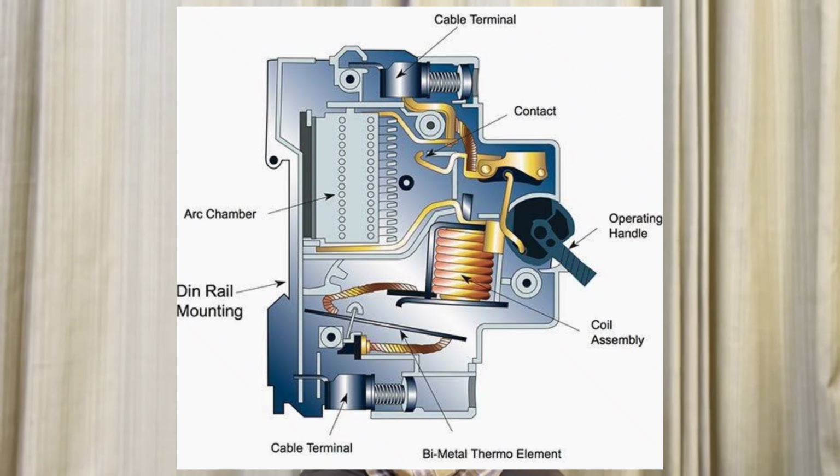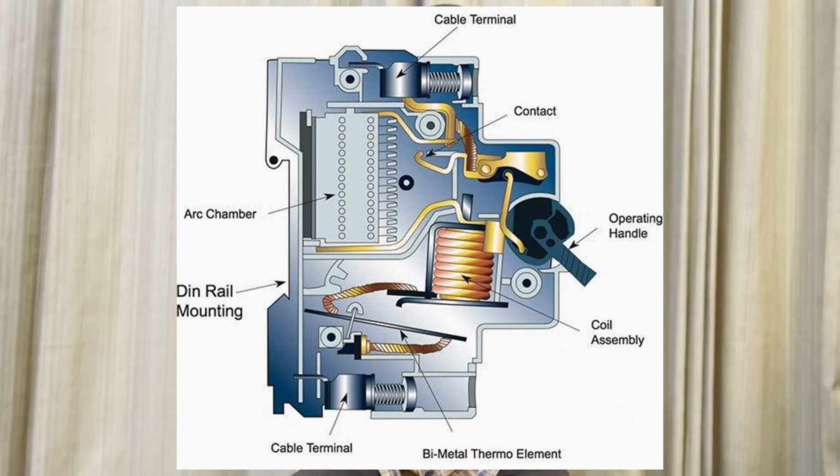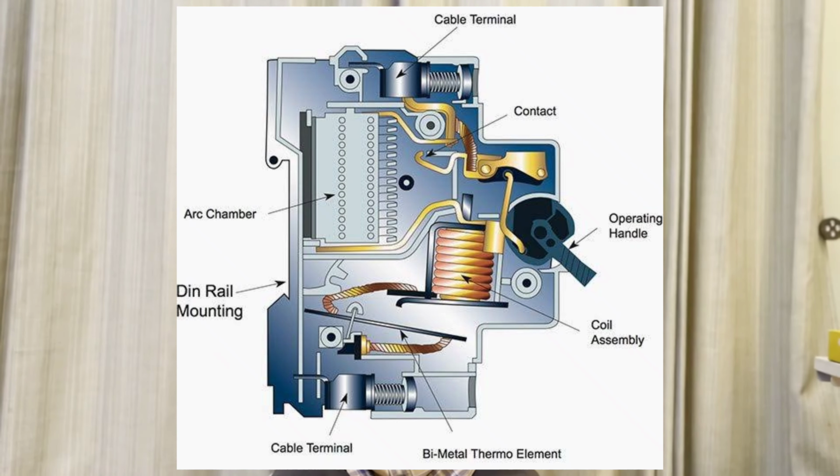In that case, our protection should be very quick and rigid, so we use a completely different method of protection in an MCB. In a short circuit condition in an MCB, it is working on a magnetic principle basically. We have magnetic coils. Whenever the current increases, our magnetic coil will get energized and a plunger, which is a mechanical device in our MCB, will get activated and the plunger will switch off the circuit. So this is how an MCB works in a short circuit condition. I hope you understand that MCB gives us two protections: one is short circuit and one is overload.